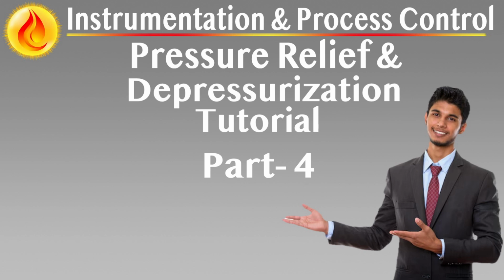Flow measurement devices in flare headers should be selected and installed to support the following goals: detecting abnormal flows that may indicate relief valve activation, system leaks, or unplanned venting. Quantifying routine flare losses to support emissions reporting and flare gas recovery initiatives. Monitoring purge gas rates to ensure proper sealing of flare stacks and prevent air ingress. Supporting diagnostics during system testing or equipment troubleshooting. Providing alarm functionality if flow exceeds expected thresholds during normal operation.